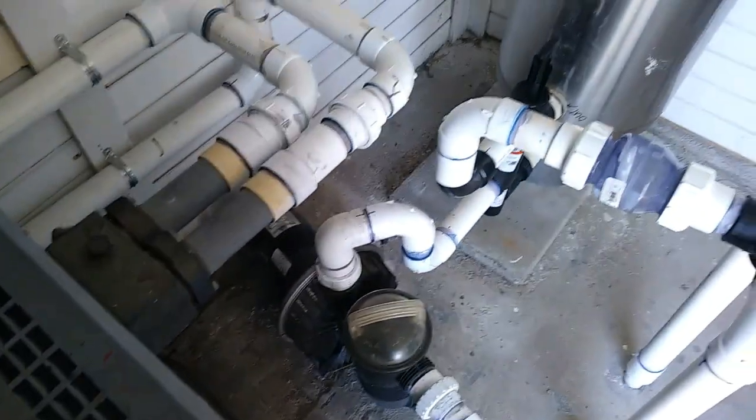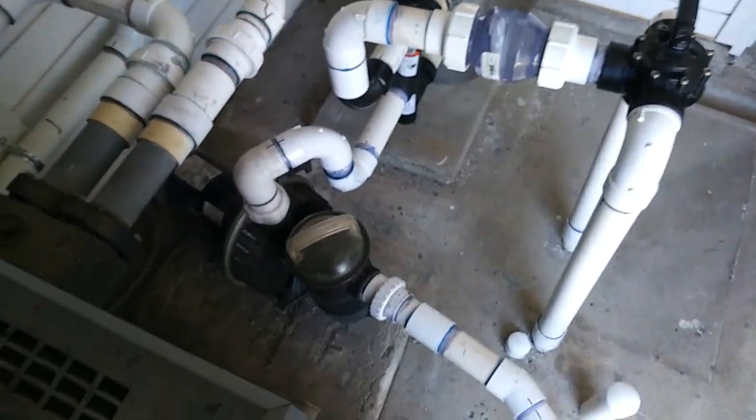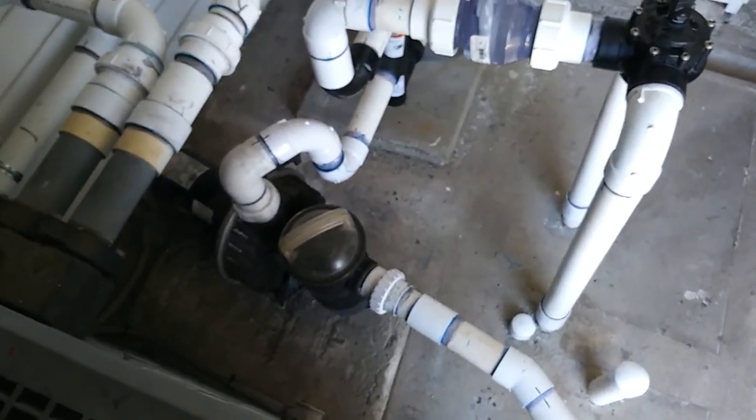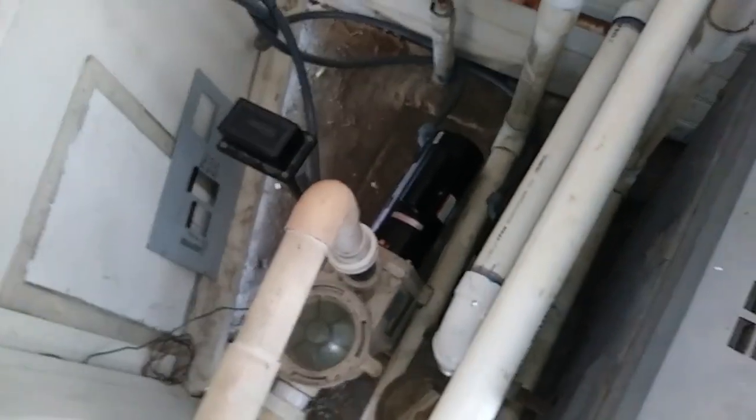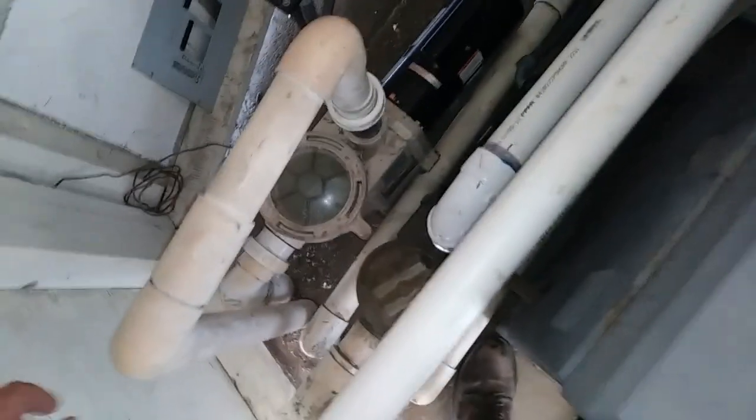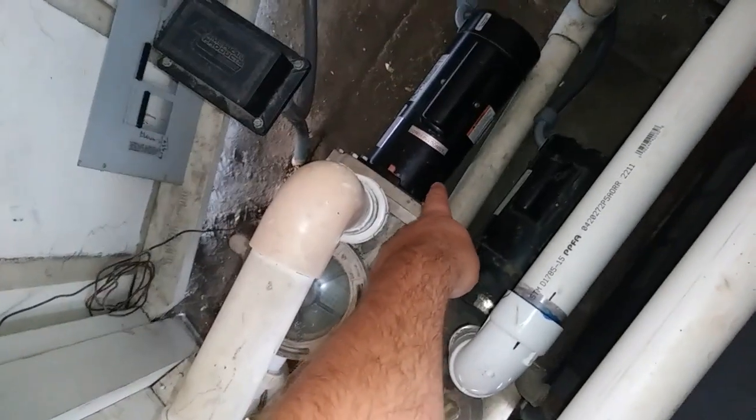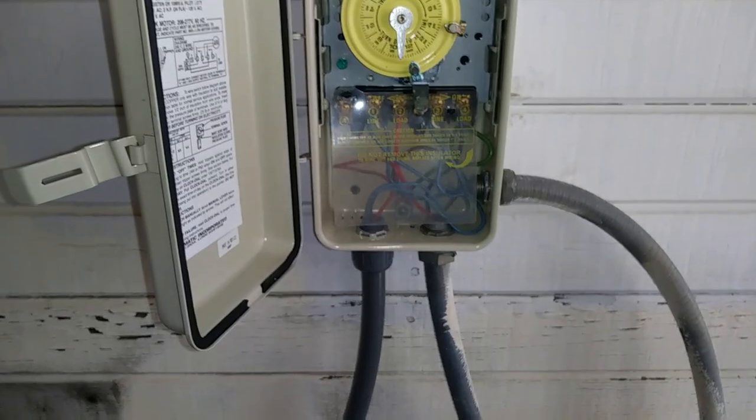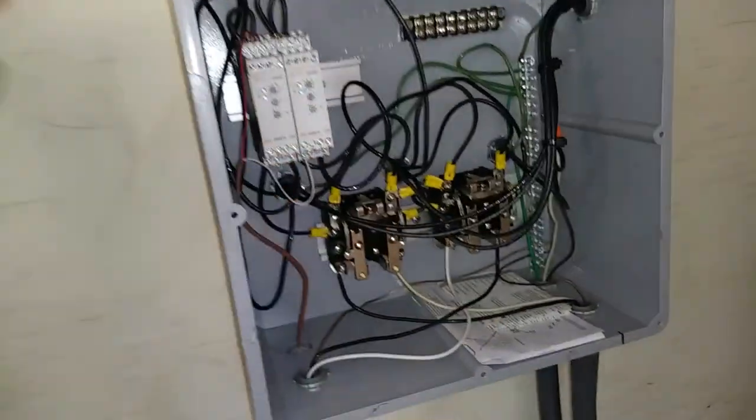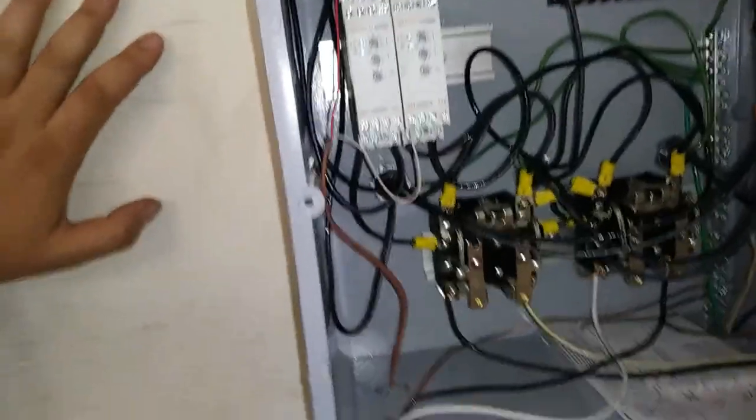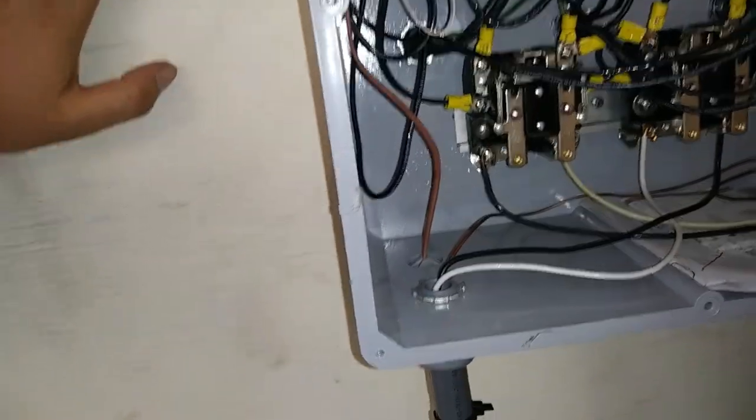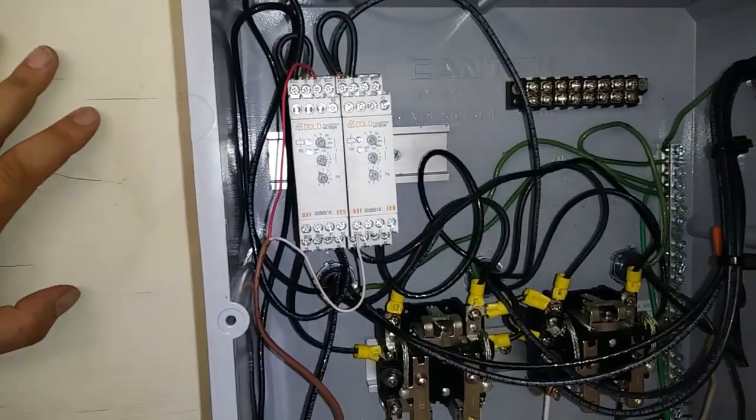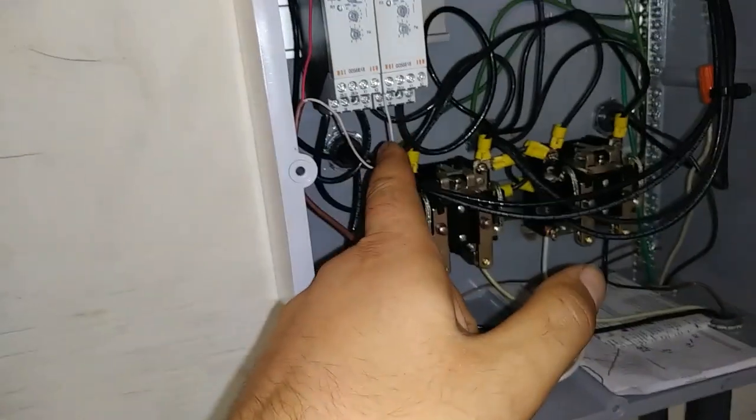So in this video, I'm just showing some of the plumbing work that was done. We added a check valve over here, replaced the backwash valve, added a union there at the pump. We replaced the motor for this jet pump, that's the primary circuit. We made some wiring changes, some changes on the timer, deleted the old control panel, and then this is the new control panel. The wiring did get cleaned up a little bit more than that before it went back together, but that was just kind of the testing phase. And the thermostat wire you see there is actually the heater enable, so it was nice to be able to accomplish that with the same relays we were already using.